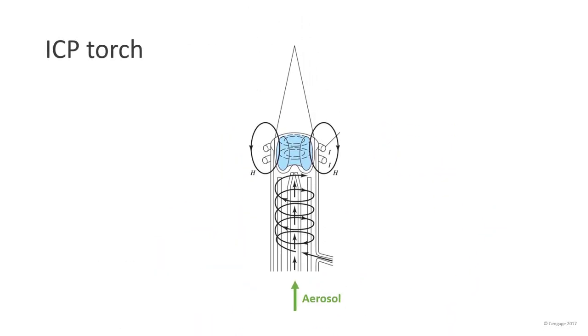The ICP torch is made of three concentric quartz tubes, which argon gas flows through. The sample aerosol is introduced via the central tube. The tangential argon plasma support flow helps cool the inner walls of the central tube.